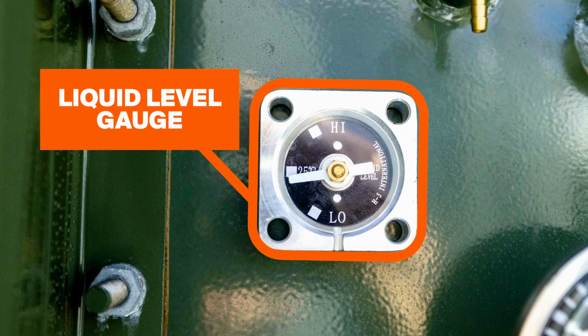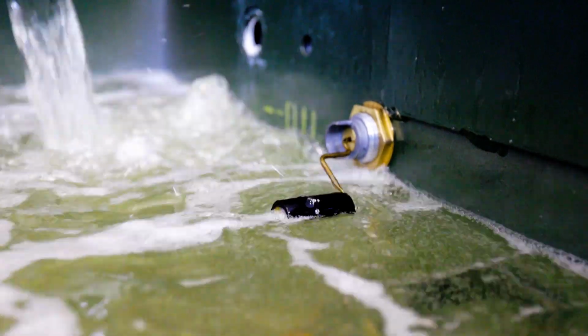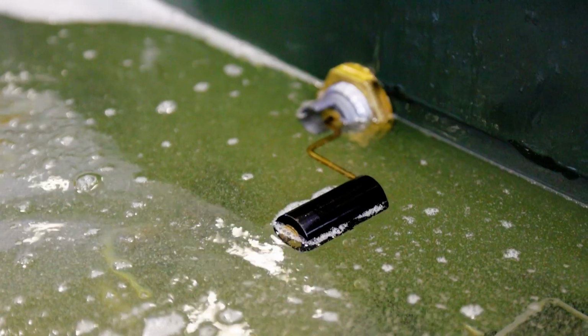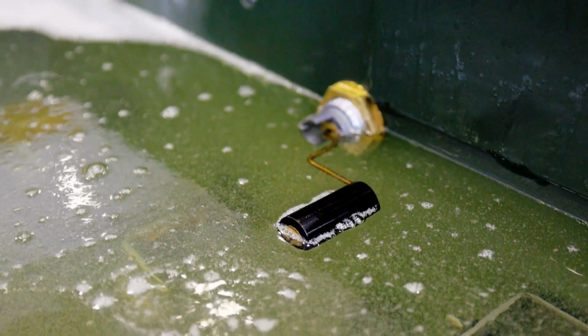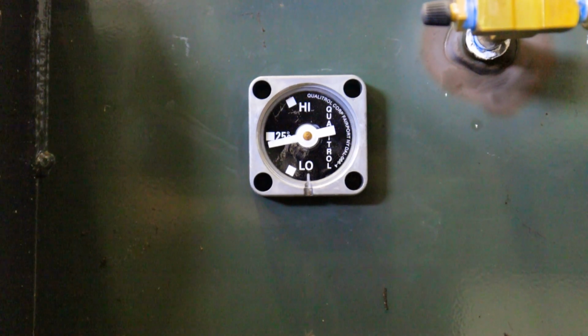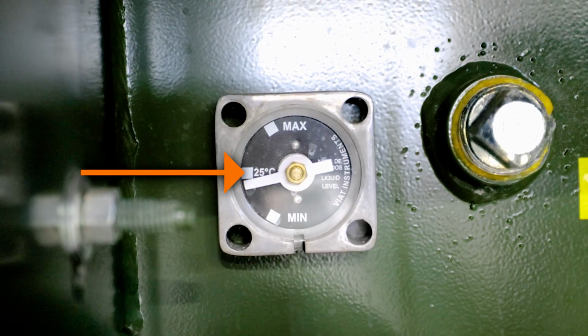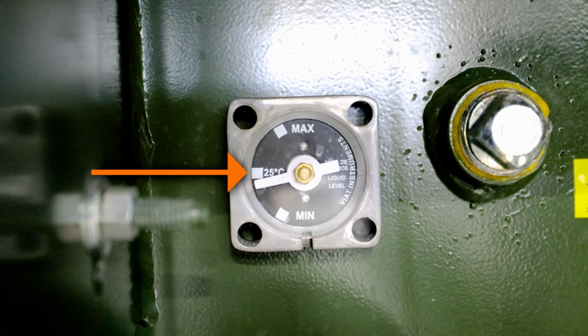This gauge monitors the transformer's oil level. A low oil level could indicate a leak or problem that needs attention. Typical oil level gauges have an internal float, much like a fishing bobber that sits on top of the oil. The indicators on the gauge mark the position of the float as it floats on top of the oil. The face of the gauge will also have a 25 degrees C temperature reference marker, since the level of the oil is affected by the outside temperature.